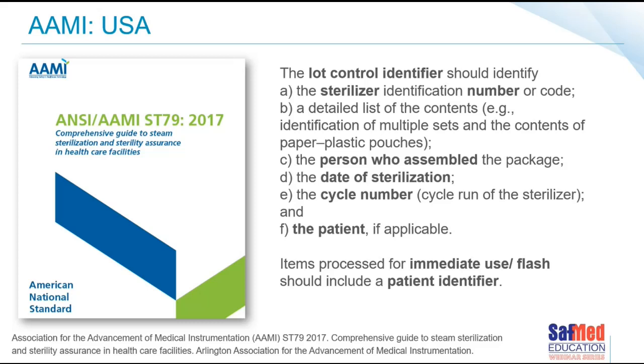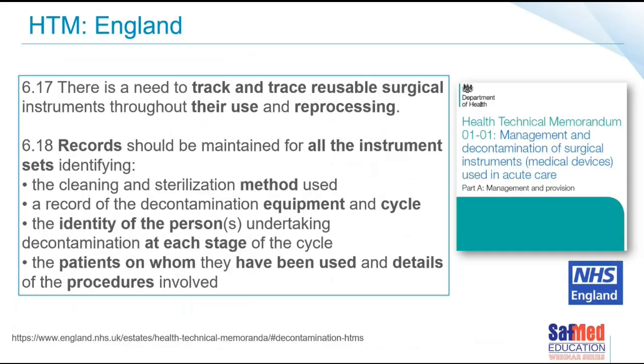AAMI ST79 also states that any item processed using immediate use steam sterilization — the term we often use is 'flash' — should also include some form of patient identifier. I wonder how many of us can actually identify every patient on whom an item that had been flashed or immediately steam sterilized was used.